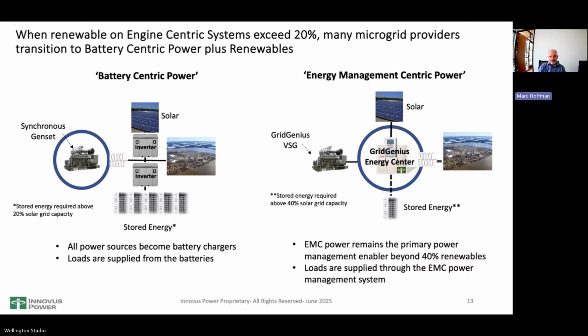Here is the alternate solution. Some operators will actually say, okay, I'm going to go add power converters to my synchronous genset because I already have to add some inverters for the solar power. I'm going to add battery inverters and a bunch of batteries, and basically everything becomes a battery charger. So to deal with all the volatility, the power out of the diesel gensets and the power out of the solar both go into the batteries, and then it goes through a power converting process and outputs AC power. Very, very good AC power, by the way.